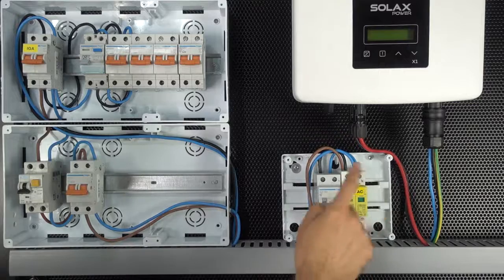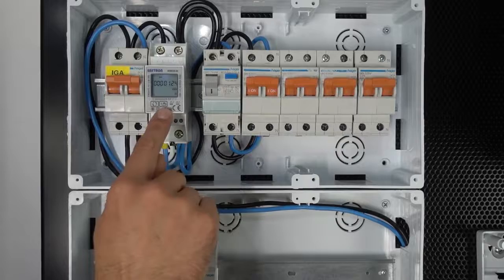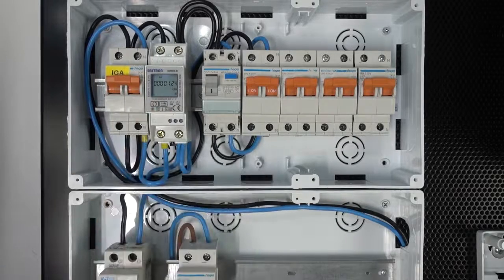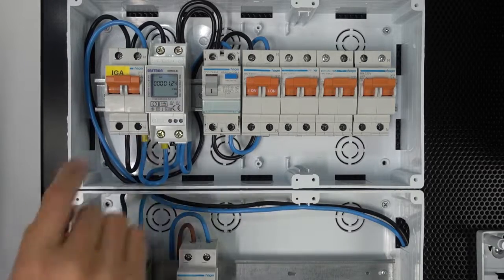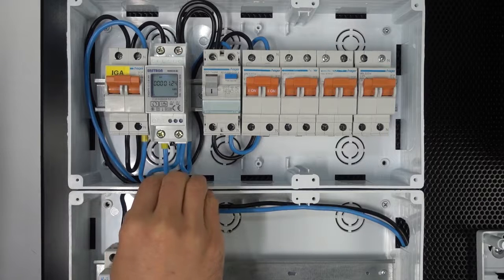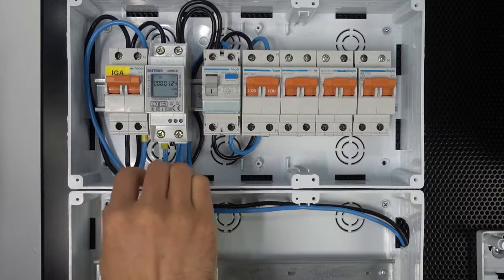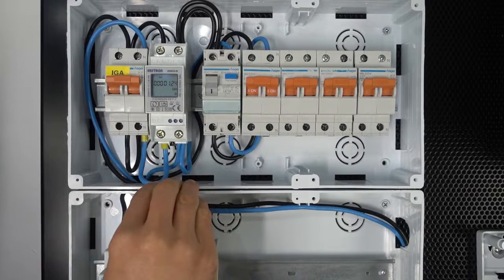In the case that we need to install an energy meter to be able to have the monitoring or zero injection, well, we would first have to follow the connection diagram of the energy meter. Since there are different manufacturers and different models, in this case you are seeing that this energy meter is an energy meter that takes the measurement directly, i.e., you have to pass through it all the energy to take the measurement.